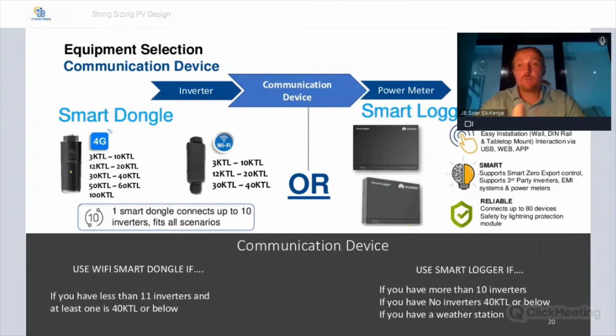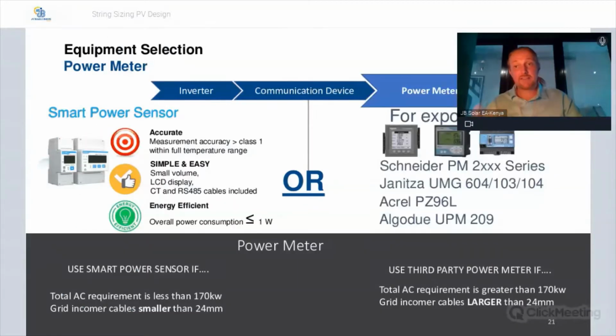So we have another webinar that goes into a little bit more detail. Today, we're just helping you do the design, choose the equipment, and we'll get to the string sizing. If you need more information on these, there are other webinars for that. And the last piece of the puzzle is the power meter. This is for export limitation, if you're not allowed to feed into the grid, or if you want to limit the feeding into the grid. On the left, we have the Huawei solution, called the Smart Power Sensor. And on the right, we have third-party meters that are compatible.